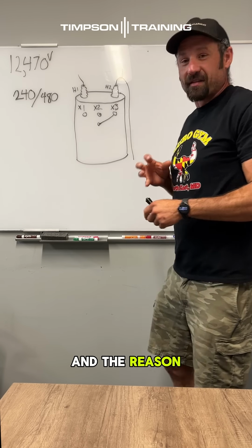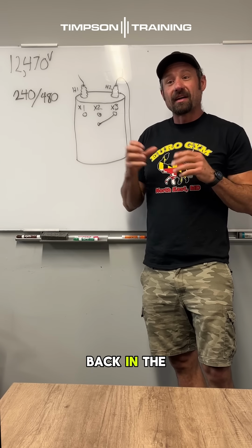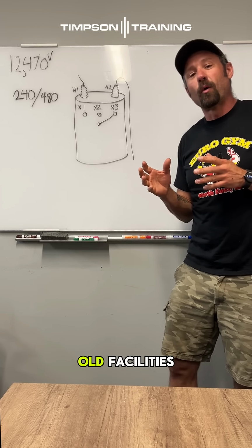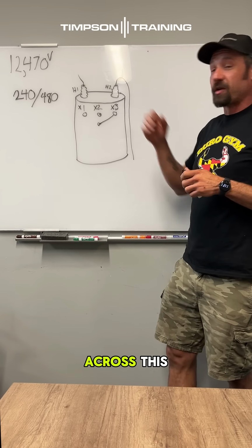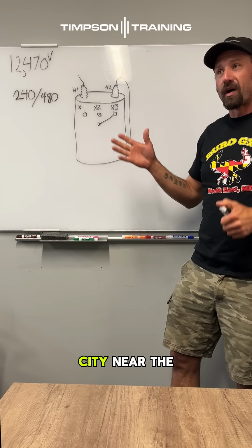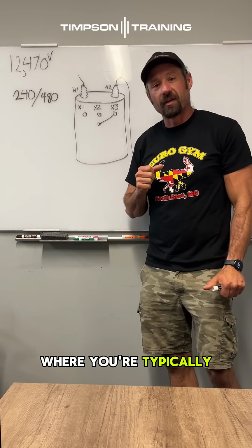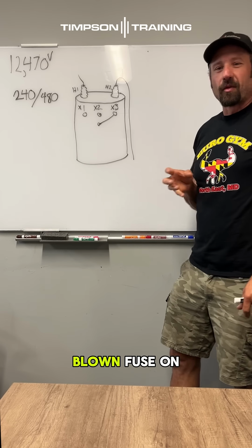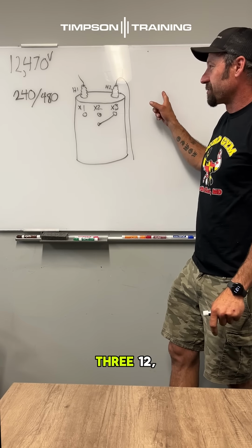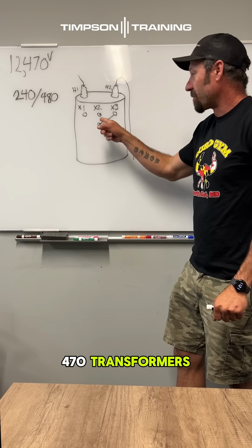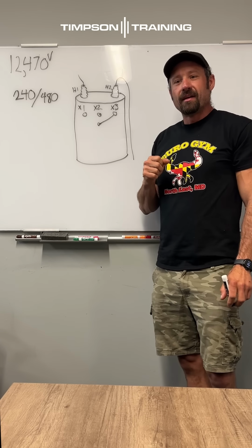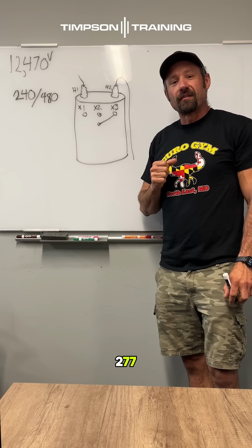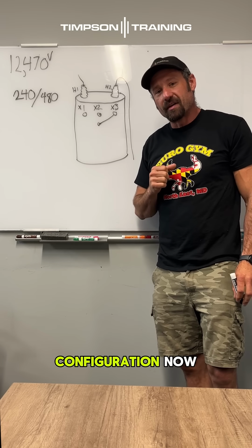This is important because back in the day, when you look at some old facilities, you might come across this in an old city near the Rust Belt area. That's typically where you'll see it—you come up and there's a blown fuse on a transformer, and you see three 12470 transformers hooked up like this. That's actually hooked up in a 277/480 wye configuration.